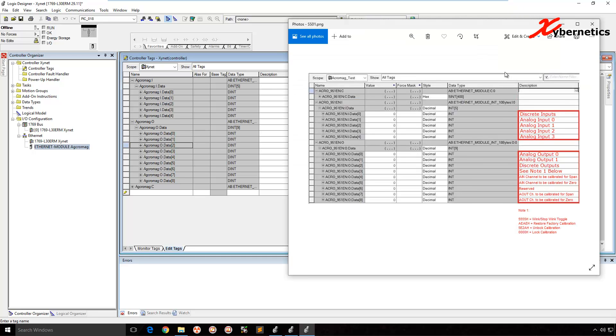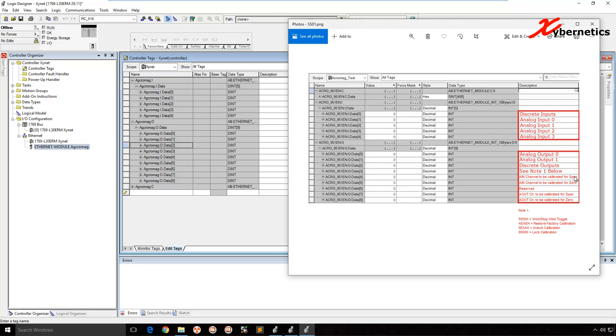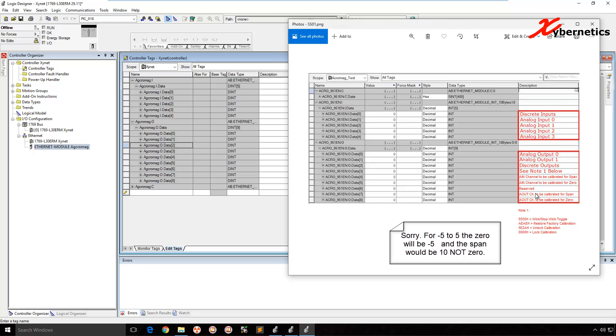And number three, three all the way to eight. They are more for configuring your device. So element number three, if you put in a hex value of, say, 5E2A, it unlocks the device and allows for calibration. So you can actually change your unipolar value from zero to 20,000 to zero to 100. So your zero will be zero and your span will be 100. Or if you want to change it to minus five to plus five, your zero will be minus five and your span will be 10. So this is a span, not the final value. Same thing for analog output. So basically element three is your trigger. And number six is reserve. I'm not too sure exactly what they use it for.